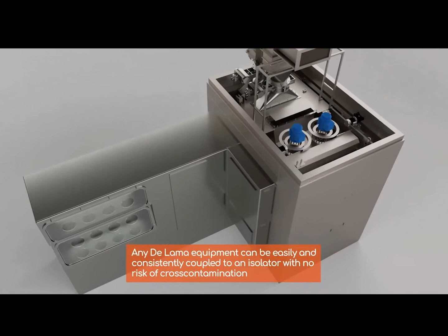Considering that De Lama is able to manufacture, as you might see here starting from the top down to the right, saturated steam or air steam mixture autoclaves, hydrogen peroxide sterilizers. When I say sterilizer, I mean log 6 reduction in high vacuum, meaning that it is a real sterilization for everything but liquid loads. Washers, decontamination units with hydrogen peroxide, or combined units, which combine one of the techniques I just showed you into one only unit, meaning that we can sterilize, wash, decontaminate in the very same equipment.